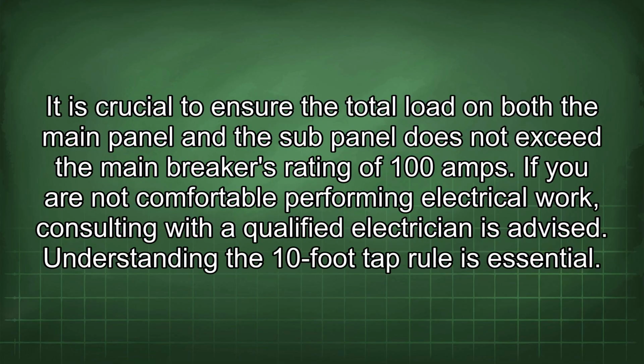It is crucial to ensure the total load on both the main panel and the sub-panel does not exceed the main breaker's rating of 100 amps. If you are not comfortable performing electrical work, consulting with a qualified electrician is advised. Understanding the 10-foot tap rule is essential.